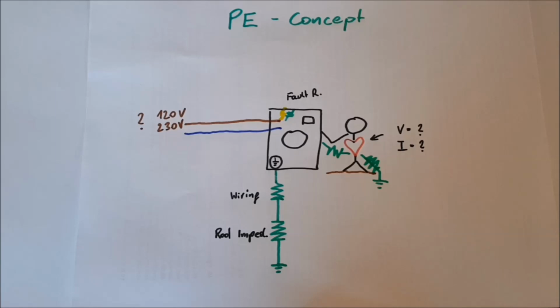Because some parts of the IT system, if you have multiple circuits which you can have if every circuit is monitored, still need protective earthing there. So the earthing electrode, when you use your own inverter, is primarily there to create the TN system in the first place. This gives you the chance that fault currents, caused by a human touching a hot wire, leak through earth and go back to your inverter, tripping one of your protective devices. Now we have to quickly talk about the PE concept.